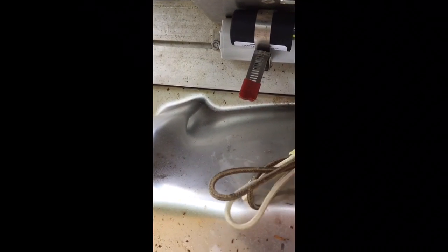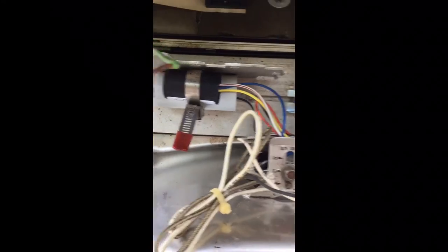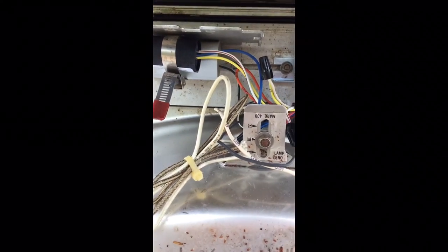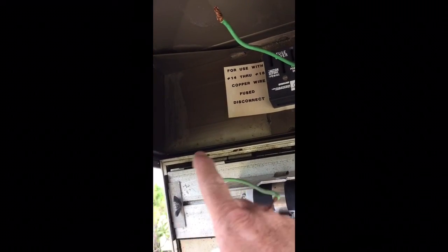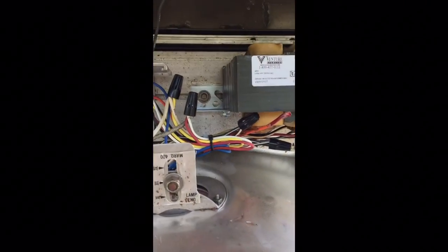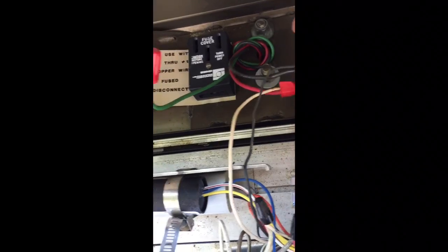That one-hand filming is killing me, that's why I don't make so many videos. I'll just wire the socket directly to the ballast. We have common, and red is for lamp, white or yellow which is X2 of the igniter. Then I will hook up the other common and the 480 volt tap to the source. Always ground your shit — because if you don't, you're an asshole. Here's the finished product: ballast tied up to the socket, lamp, common, 480, common, ground.